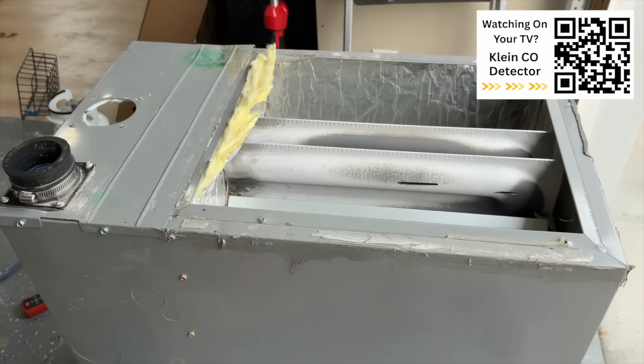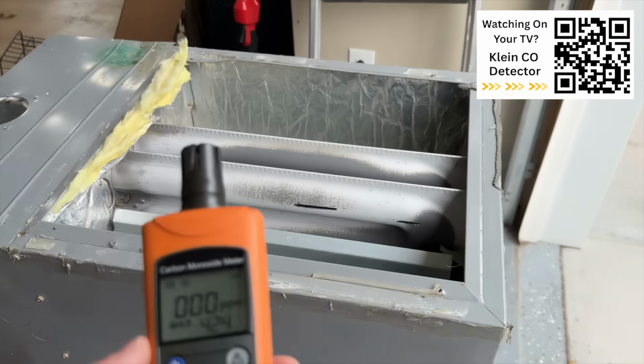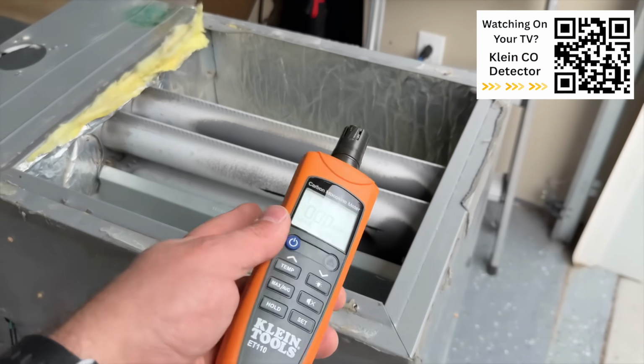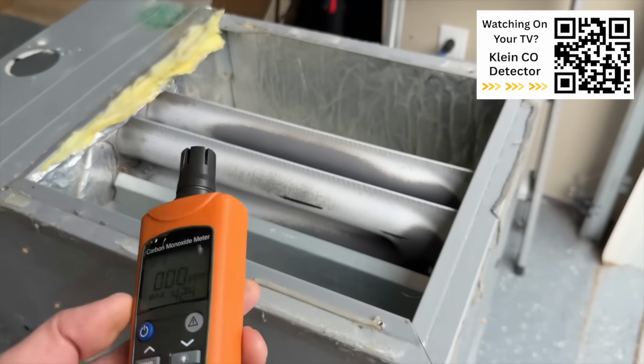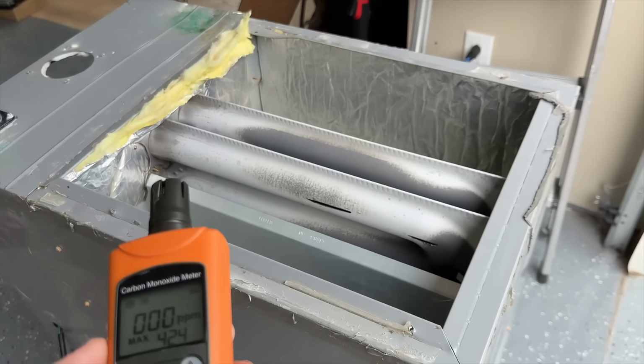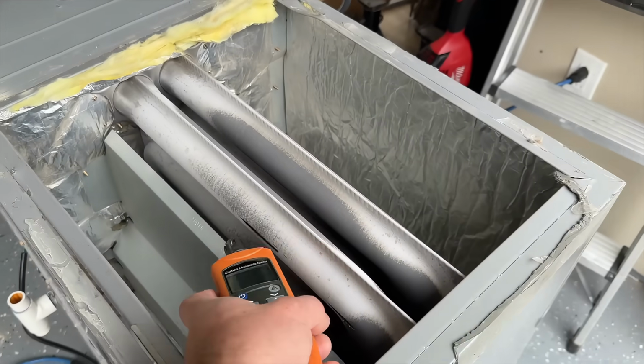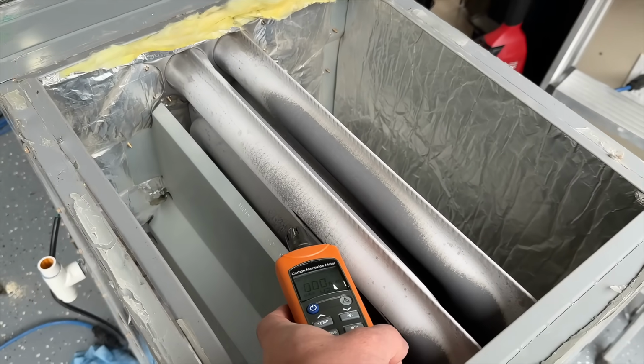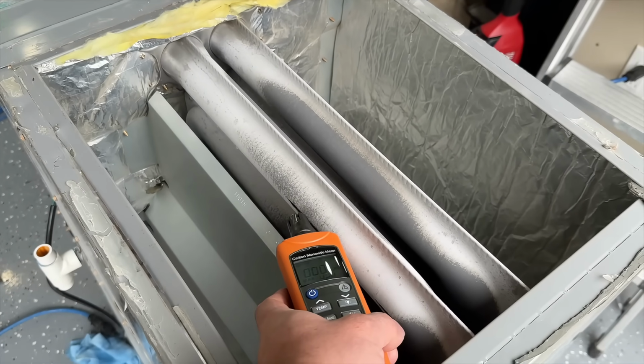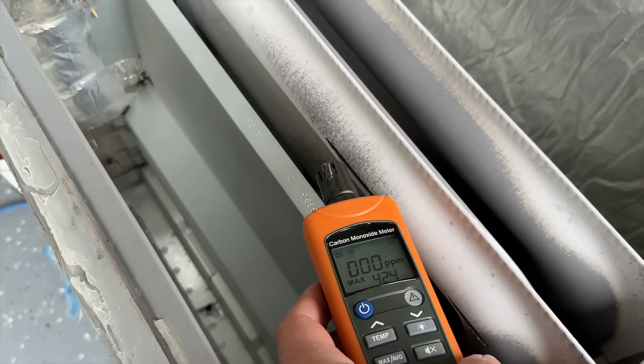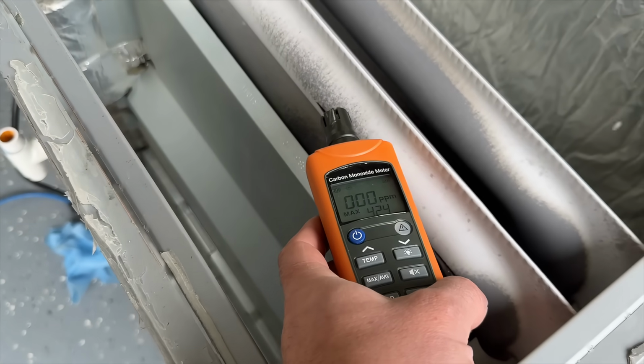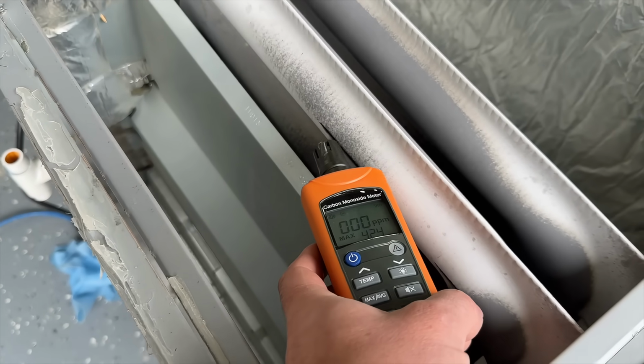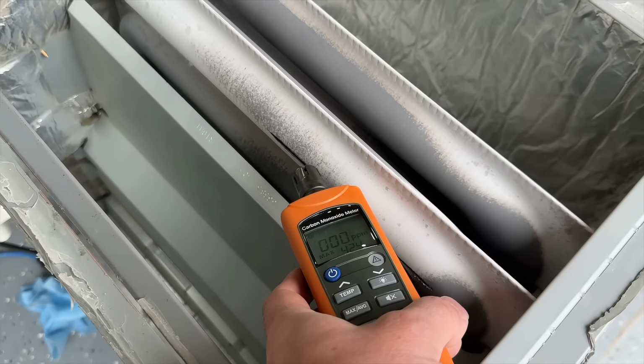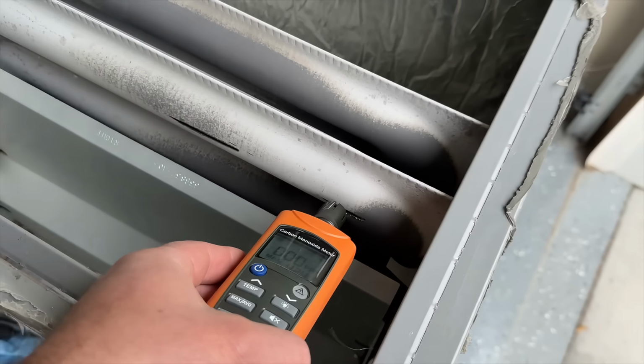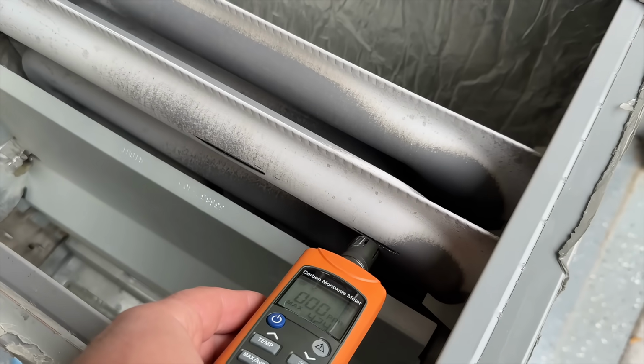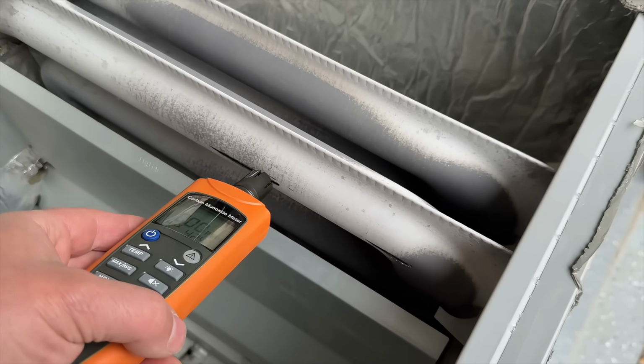Now the blower motor just came on, and I want you to check this out. We're right here next to the heat exchanger where supposedly it's sending carbon monoxide out. And notice what this is reading. Literally right next to it, zero parts per million. Hovering right next to it, and we get nothing.